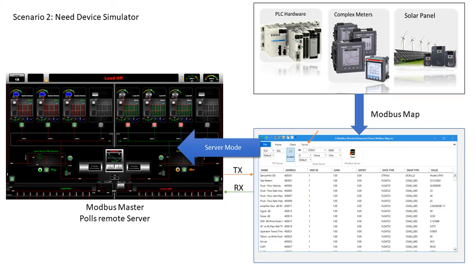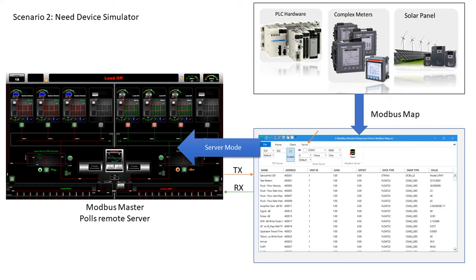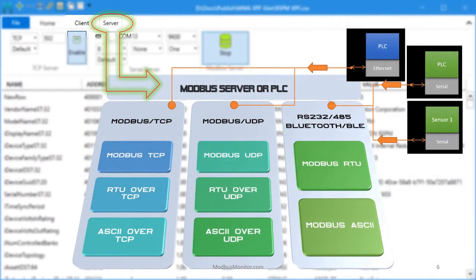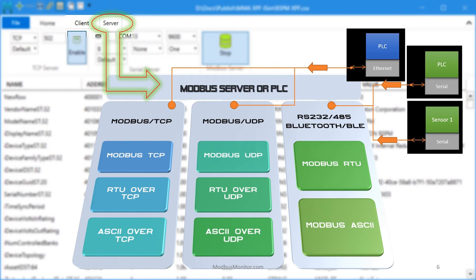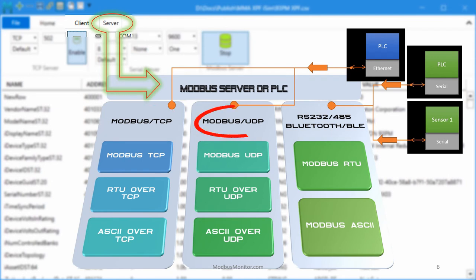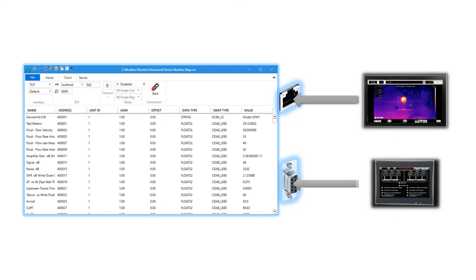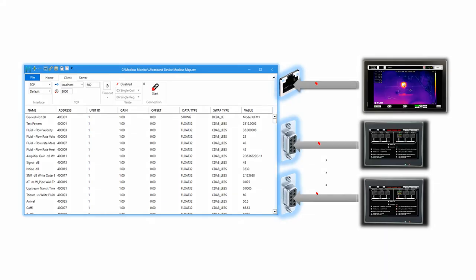The same scenario can also help validate future software releases in a simulated environment to find any problems. The Modbus Monitor XPF also has a server or Modbus slave mode integrated. This is an advantage over other apps. There is nothing extra to buy, and the same Modbus map is used in client mode. Once the Modbus map is set up in the program, the server and client share the same map. Server mode can be configured to send data in Modbus TCP or UDP or Modbus RTU. Note the Modbus TCP server and Modbus RTU server can be used simultaneously. In other words, Ethernet and serial ports can be enabled at the same time.